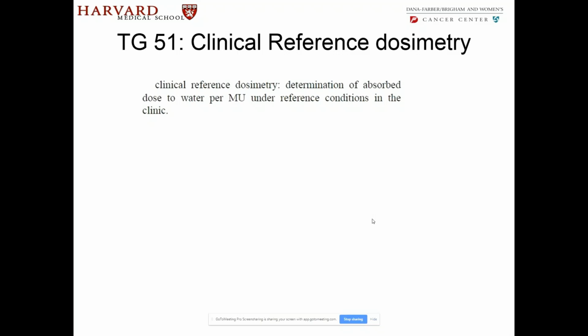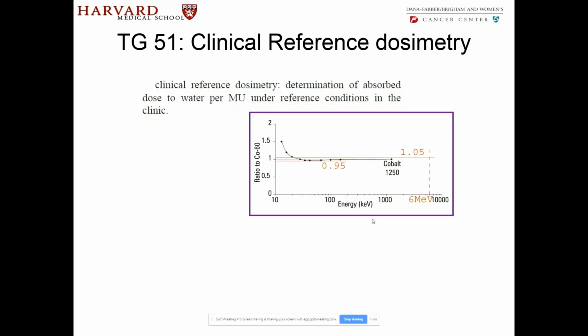That's what we are going to set up using TG51. We are going to tell the machine, look, only when you have this particular monitor unit will this correspond to this particular amount of dose being given. Okay, so to do that, let's say you start with an ion chamber. We always start with an ion chamber for that.